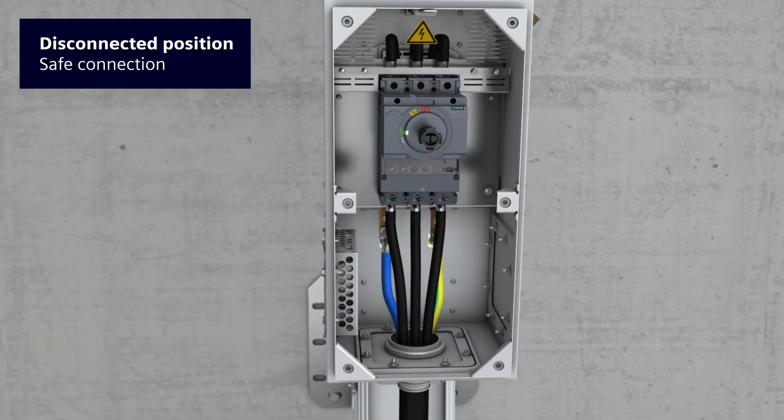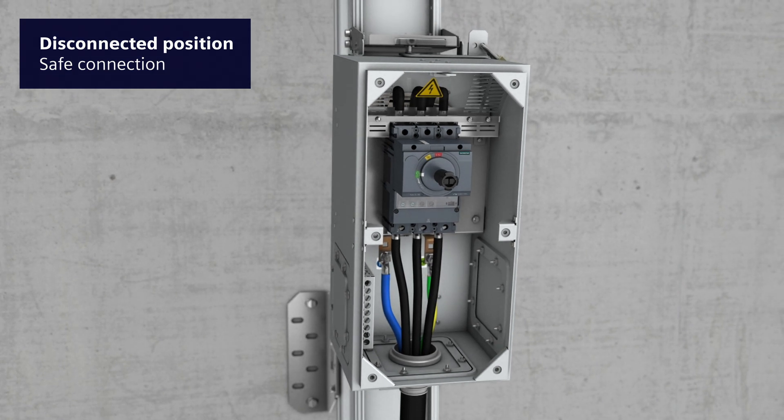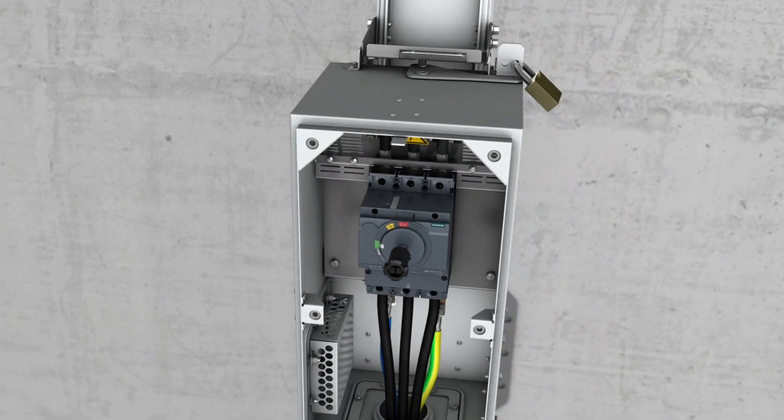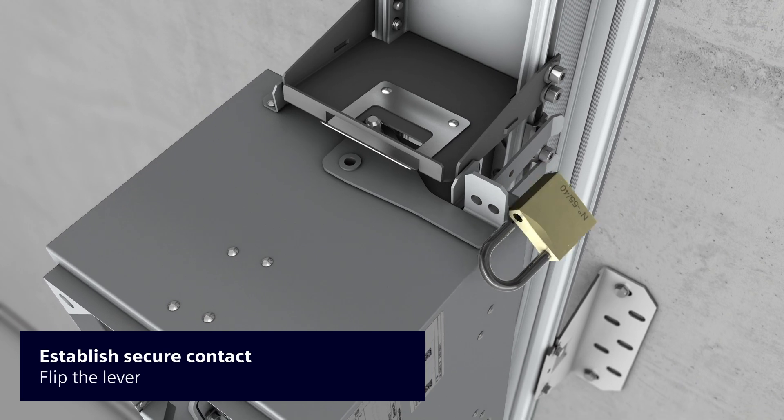The electric connection of the consumer to the tap-off unit can now be carried out safely by simply connecting the consumer cables. Electric contact between the tap-off unit and the bus bar system must not be established before all cable connections have been completed and secured.